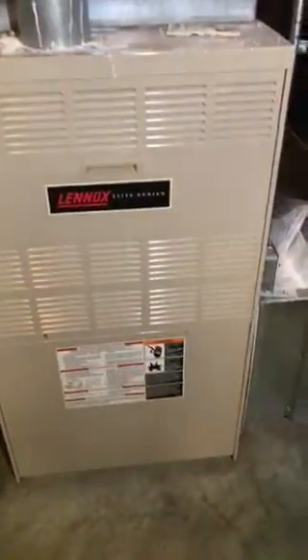Here we are in South County. She's got a five-ton system she's looking to replace — the furnace, the air conditioner, and the water heater. First thing you see, she's got a one-inch filter and only one filter, so we need to redo this return. I'll get you the dimensions on that.